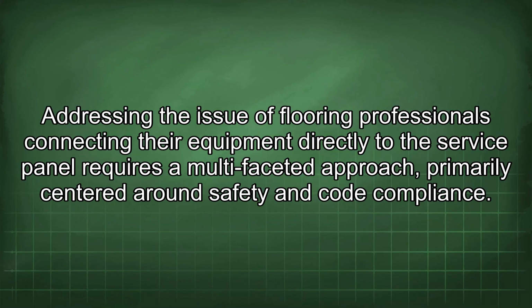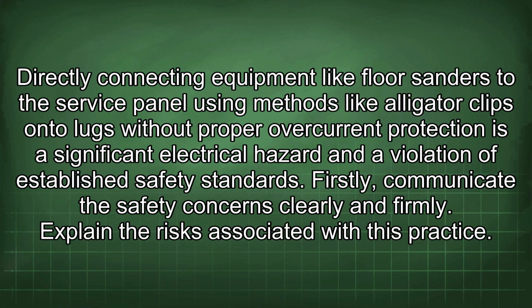Addressing the issue of flooring professionals connecting their equipment directly to the service panel requires a multifaceted approach, primarily centered around safety and code compliance. Directly connecting equipment like floor sanders to the service panel using methods like alligator clips onto lugs without proper overcurrent protection is a significant electrical hazard and a violation of established safety standards.